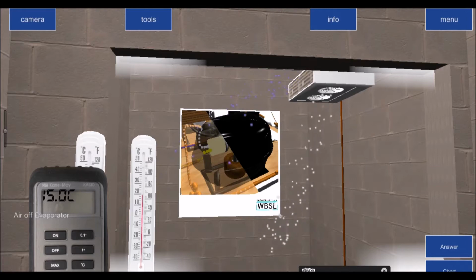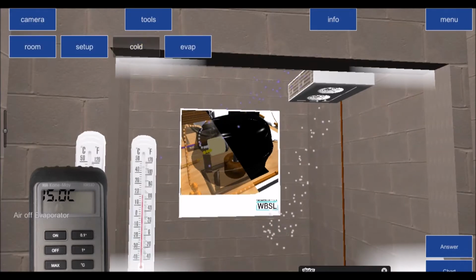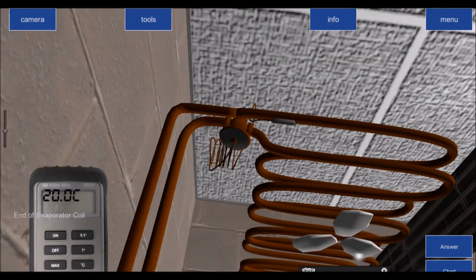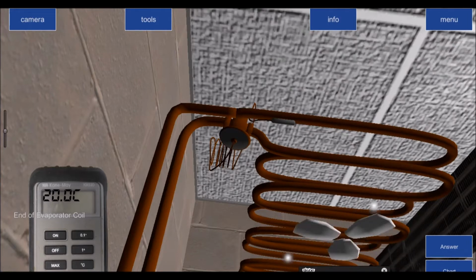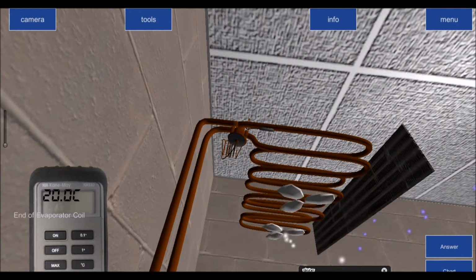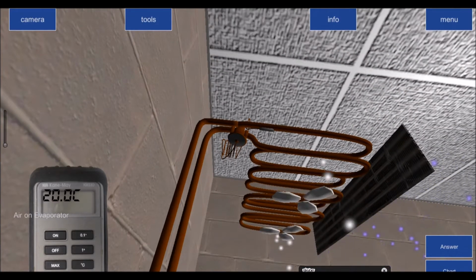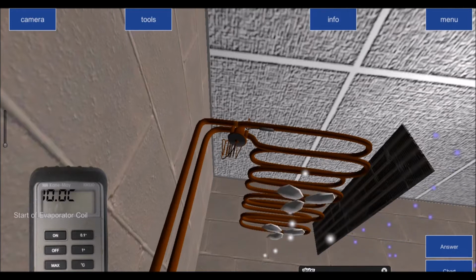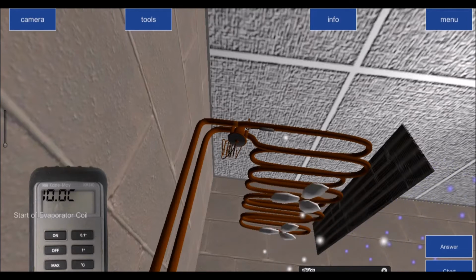And in order for me to determine that the evaporating temperature we got from inside the evaporator is normal, we have to work out what I refer to as the delta T total. The delta T total is the difference between air on temperature, which we have here at 20 degrees, and evaporating temperature, which is the temperature of the liquid refrigerant vapor mixture inside, or the saturation temperature of the refrigerant inside the evaporator. So in other words, evaporating temperature is the temperature of the refrigerant inside the evaporator versus the temperature of the air coming onto the evaporator.